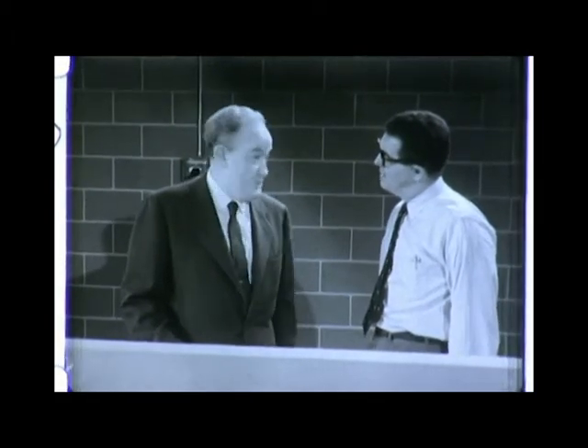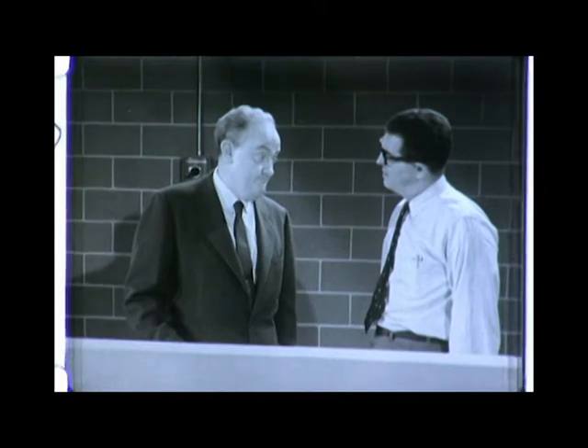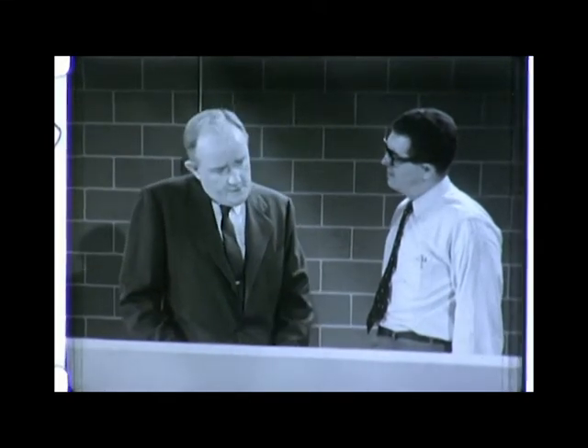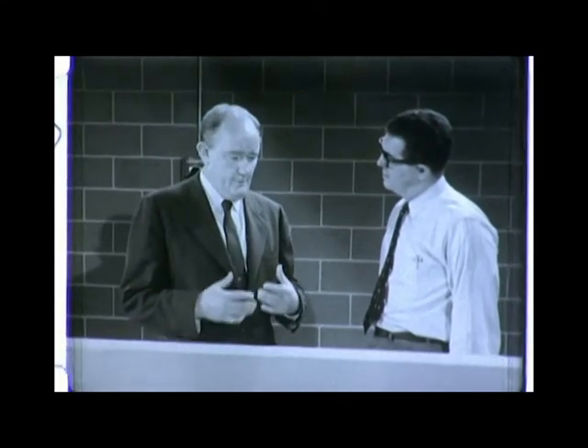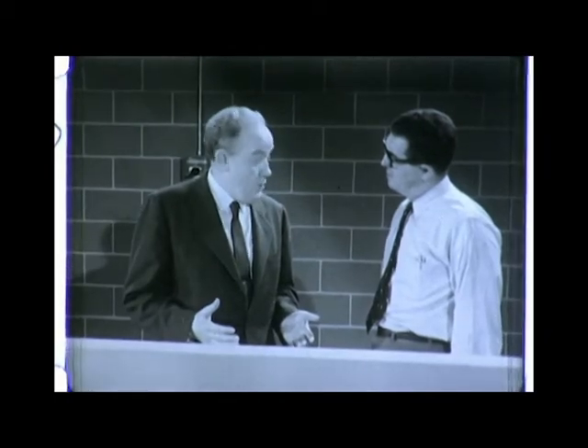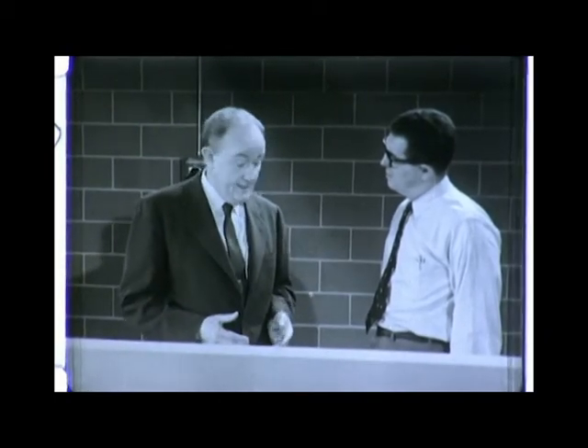With ordinary fuses, yes. With CLF fuses, no. You see, ordinary fuses can change characteristics because of aging on the shelf, or due to weakening by current surges on the line.